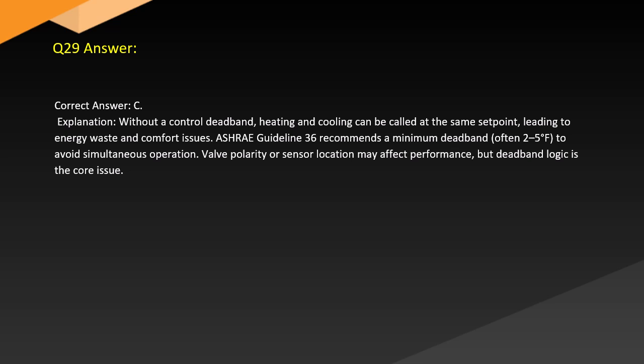Answer. Correct answer: C. Explanation. Without a control deadband, heating and cooling can be called at the same set point, leading to energy waste and comfort issues. ASHRAE Guideline 36 recommends a minimum deadband, often 5 degrees, to avoid simultaneous operation. Valve polarity or sensor location may affect performance, but deadband logic is the core issue.